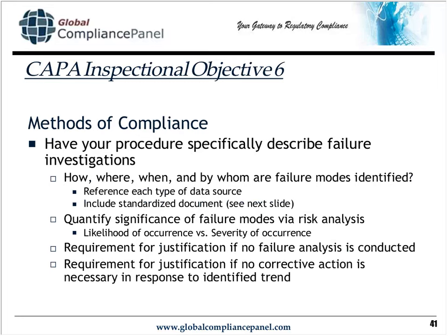The way to comply with this is, first off, to make sure your procedure describes your own failure investigations, the classic how, where, when, why, and who. Well, maybe not necessarily why in this case, but how are failure modes identified? By explicitly referencing each type of data source. And many firms I know have a standardized document, and I'll show you that momentarily, on which all of your failure investigations are documented. It works out really well because once the inspector has seen that document, he or she gets comfortable with it as the inspection progresses.